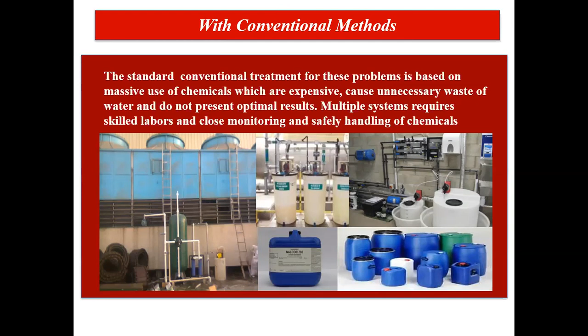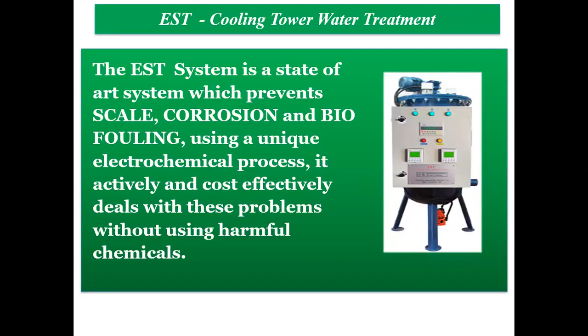So EST is a modern-day technology, called non-chemical cooling tower water treatment, or electrochemical scale treatment system, EST. It's a state-of-the-art system which prevents scaling, corrosion, biofouling, and also reduces blowdown with a single piece of equipment. Those are the basic components of the EST. We'll require that for you to know because we'll have that discussion in the next slides.